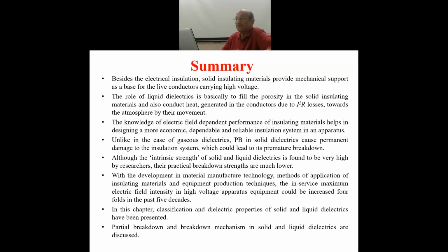The role of liquid dielectrics is basically to fill the porosity in the solid insulating materials and also conduct heat generated in the conductors due to I square R losses towards the atmosphere by their movement. By the movement of oil, heat is transported from the windings to the outside atmosphere. And this is now also being replaced when gas-filled transformers are used. There is no oil in it. The gas does the same job as the oil.